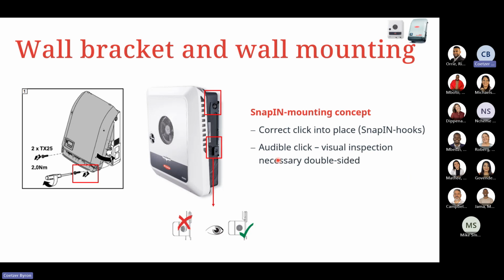So how would you know if it is correctly done? You'll see there are two simple SnapIN-hooks on the unit itself, and there's a visual check to make sure that it is clicked into place on the Gen24s. Whereas with the SNAP inverters, we have to simply fix two screws that are Torx 25 in size. We need to at least tighten them to 2 Newton meters in order to make sure that the unit is correctly fastened in place. So again, the SNAP inverter's wall bracket is a simple mounting and also a connection point for the unit itself, whereas on the Gen24, it is simply a wall mounting bracket for the unit.